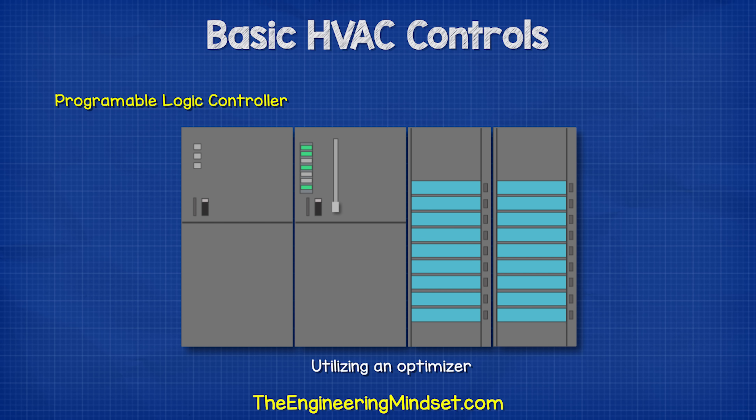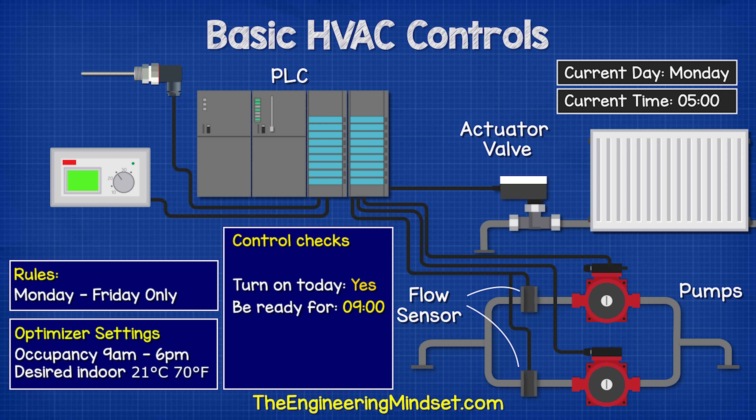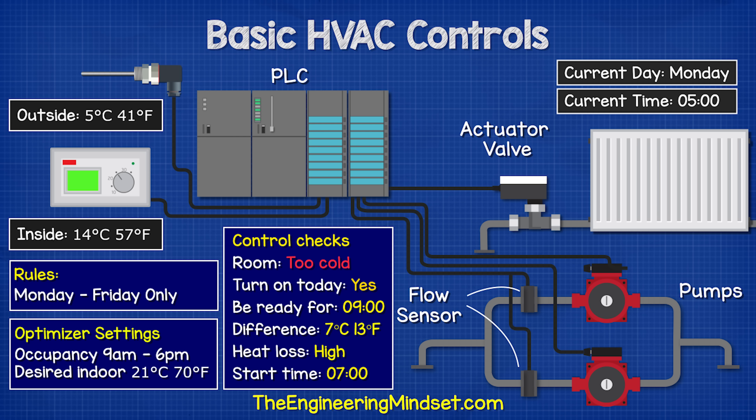A more sophisticated system, typically used in much larger buildings, will use an optimizer. For this example, we have it connected to a programmable logic controller. This will check with the clock: should the heating turn on today, and if so, at what time will the building be occupied? The clock replies yes — the scheduled occupancy time is 9 a.m. The PLC checks the current temperature of the room and calculates the difference between this and the desired temperature. It then checks the outdoor temperature to calculate how long it will take to heat the building, because on a cold day it will take longer, so it will need to start earlier.